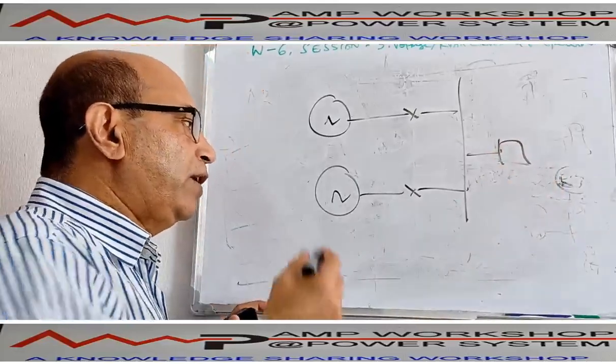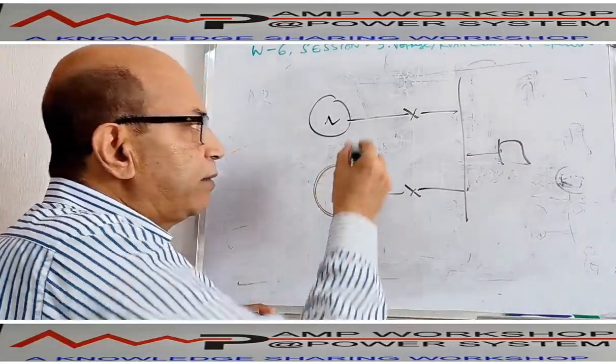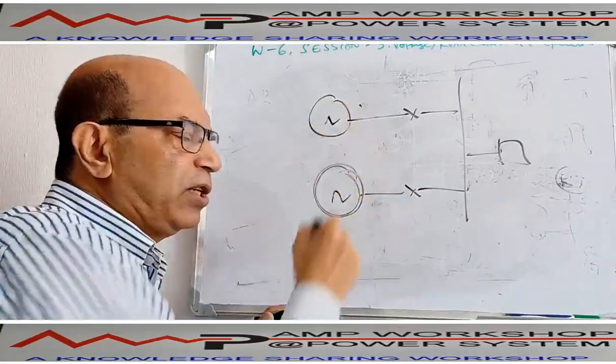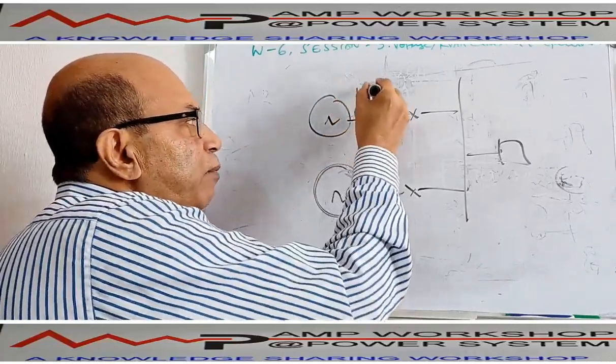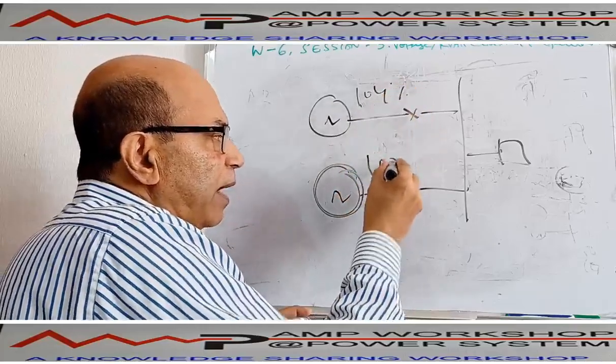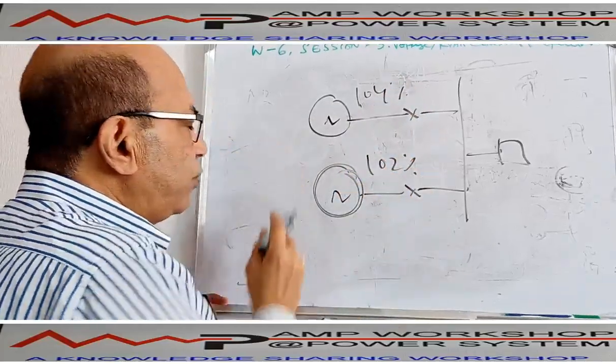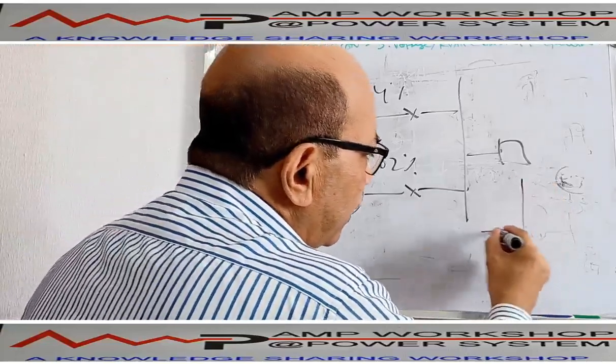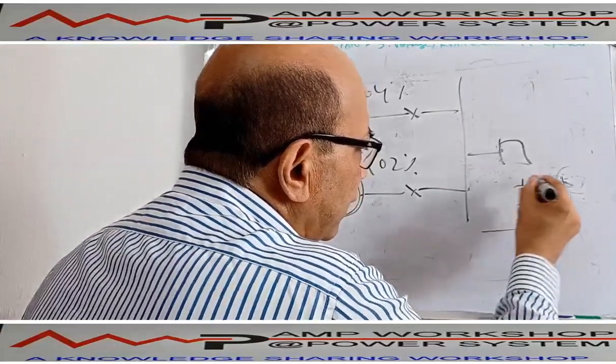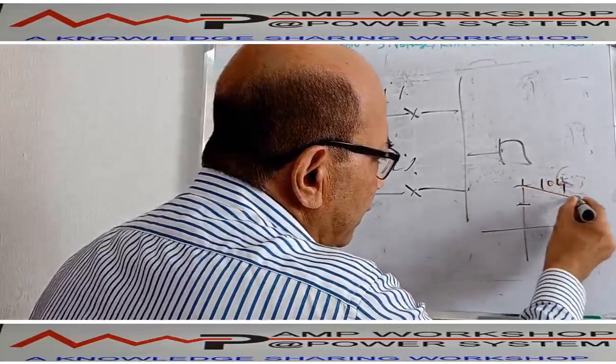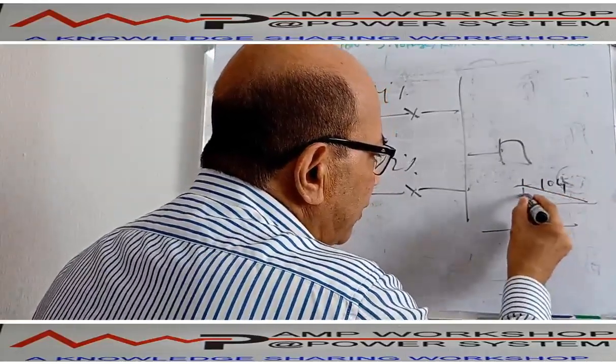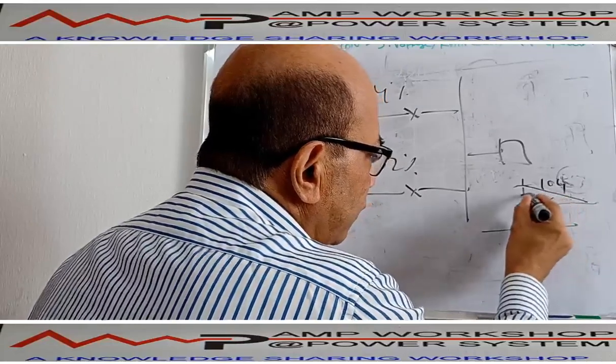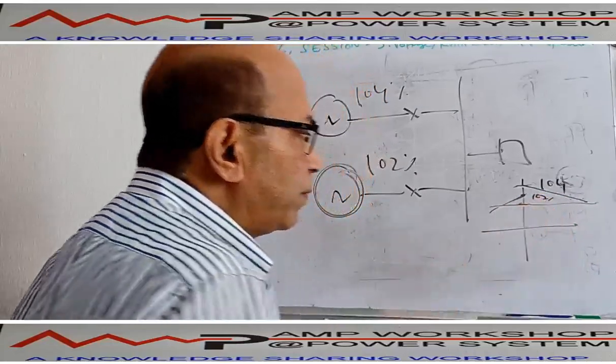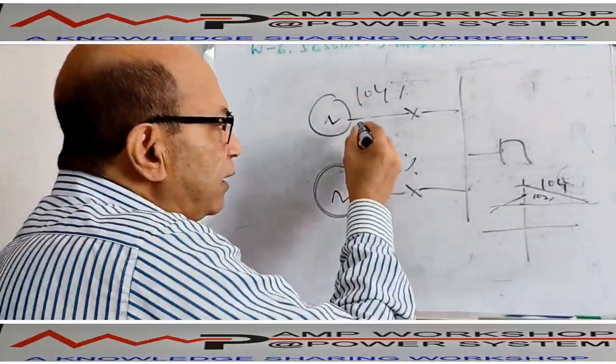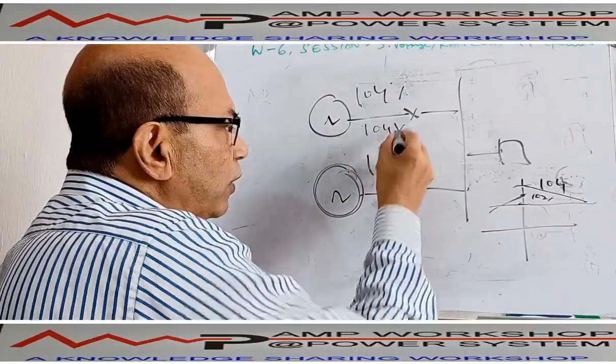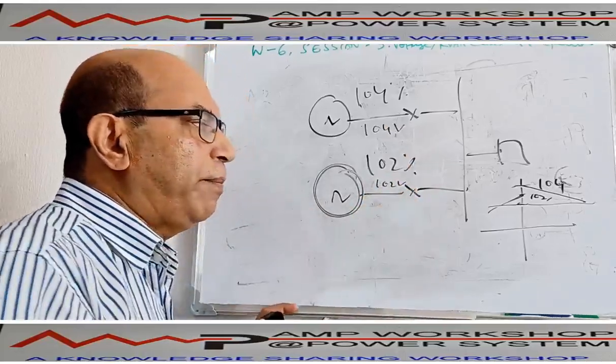Now, for any reason, if this generator voltage is different, or suppose there is a different droop setting, this machine running in droop mode has 104% droop, and this machine may have 102% droop. Then what will happen? If you see the characteristics of these two machines, they will be different. This is 104, this is 100%. Suppose this machine's characteristics are like this, and this machine's setting is 102%, so this machine's droop is like this. When both machines are running, this voltage is 104 volt and this voltage is 102 volt. Then what will happen?